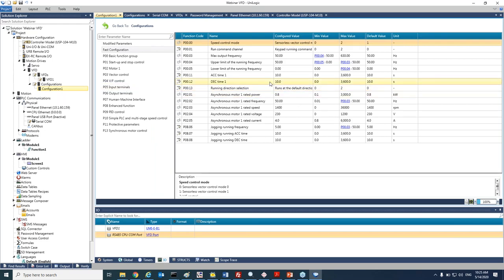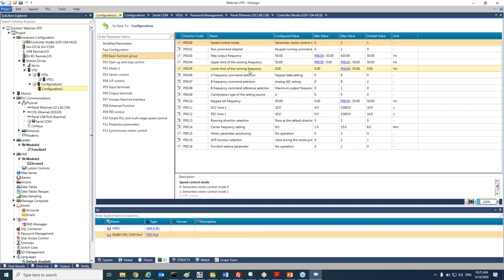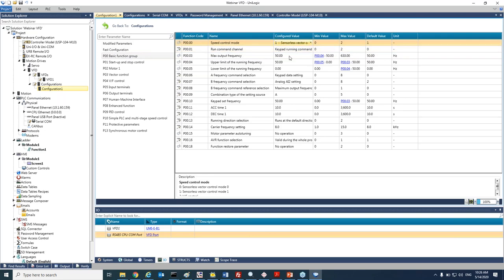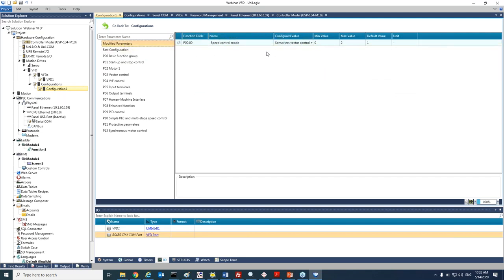A very unique feature that we have here is a modified parameter. For example, if I would like to change a specific parameter and work with all the defaults, I can come here to the speed control and change it from working sensorless vector control — I will change it from 0 to 1. If I go now to the modified parameters, you can see that I changed only one parameter, and we will see later on how we can download that specific parameter very quickly in our application.